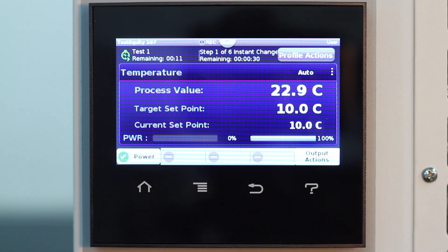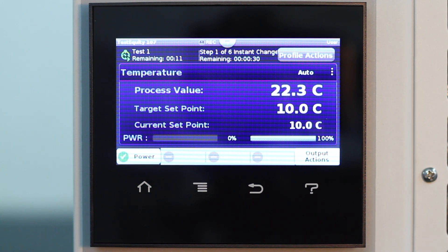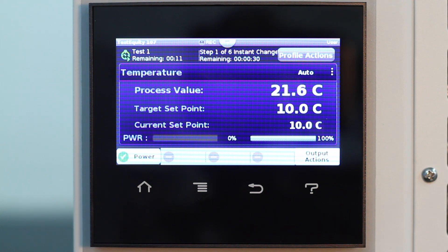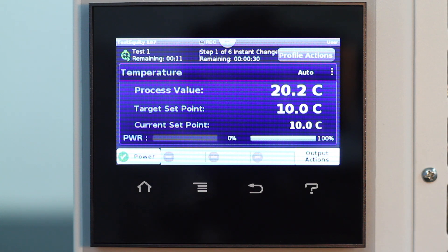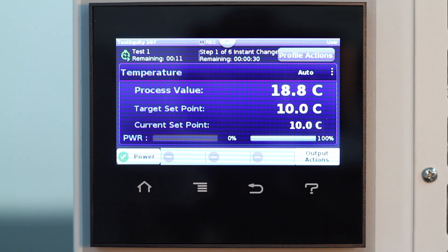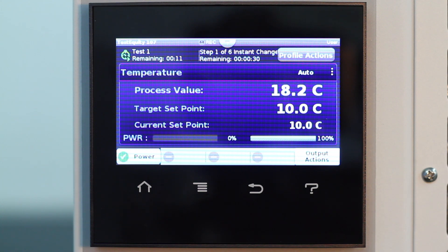Back at the home screen, we can see the target set point, which is the temperature we want to achieve, current set point, which is the instantaneous set point in a ramp, and process value, which is the temperature inside the chamber. On the top, we can see the step number, type, and time remaining.